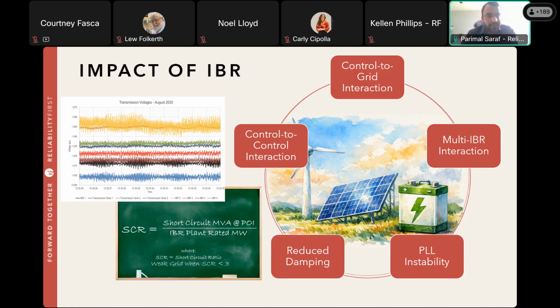It's a specific device that's installed on the grid following IBRs that essentially tracks the parameters of the grid that are then utilized for the control algorithms that are part of the grid following IBR technology. I'll start with the control to control interaction. So what happens is in an IBR plant, there are numerous IBRs, which means the plant might have 100 solar panels or thousands of solar panels, and each panel has its own local controller. And then there's a plant-wide controller called a power plant controller.